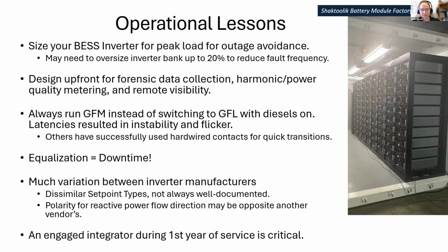Another thing we expected was to switch between grid forming and grid following. Whenever the diesels were on, we expected to run in grid following, but there were communication latencies, instability, and flicker, and it didn't actually work very well. So we actually run in grid forming mode all the time. I know others who do switch back and forth, but to do that successfully they have hardwired contacts to capture those transitions and avoid the latency issues of doing it over communications.